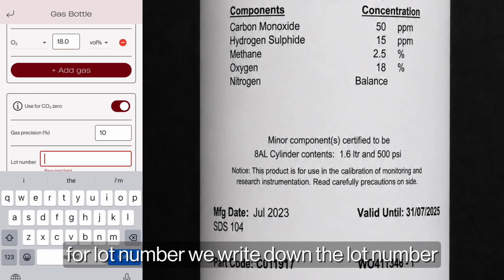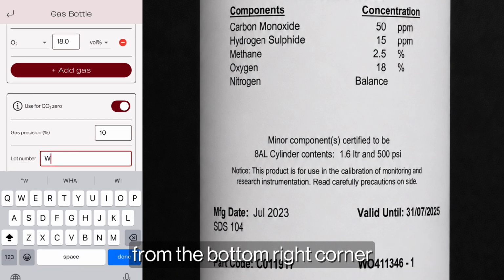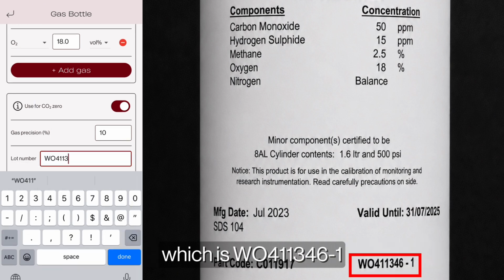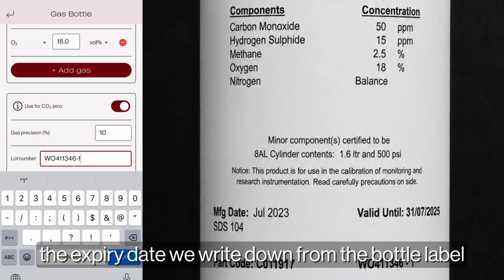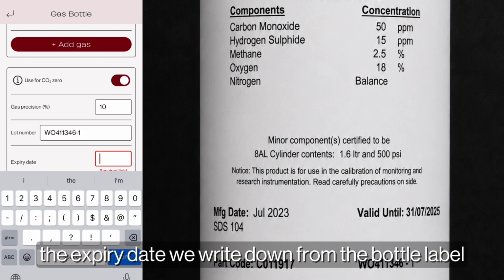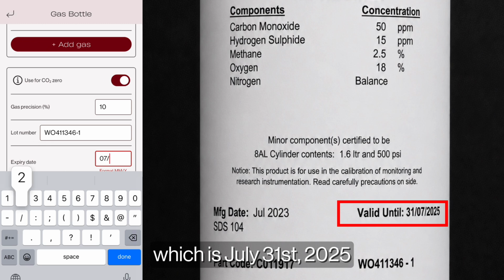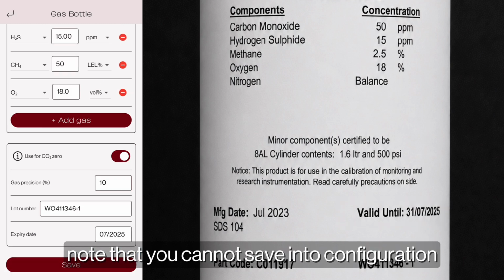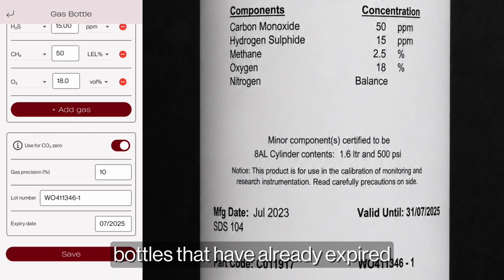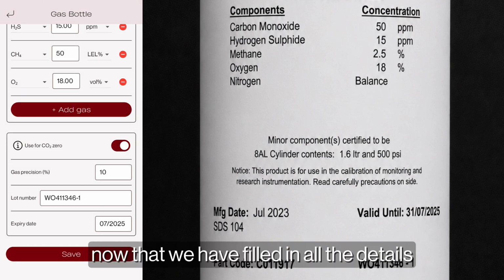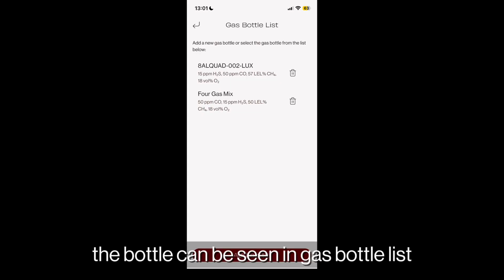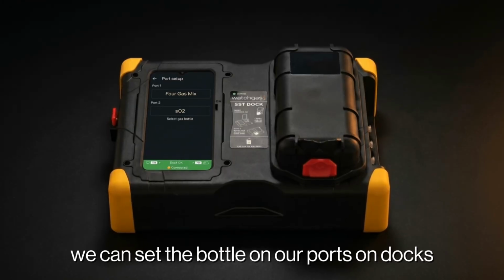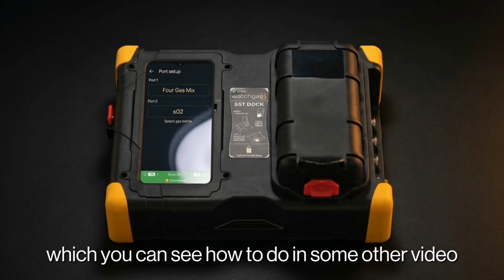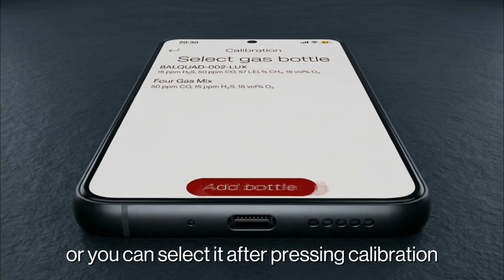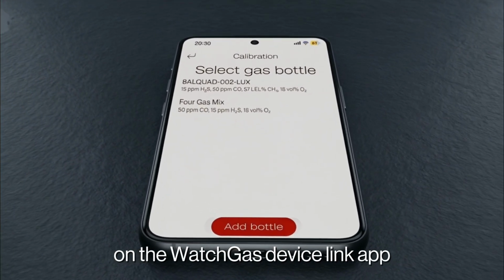For lot number, we write down the lot number from the bottom right corner, which is WO411346-1. The expiry date, we write down from the bottle label, which is July 31st, 2025. Note that you cannot save into configuration bottles that have already expired. Now that we have filled in all the details, we can save the bottle. The bottle can be seen in Gas Bottle List with the name we gave it. We can set the bottle on our ports on docks, which you can see how to do in some other video, or you can select it after pressing Calibration on the WatchGas device link app.